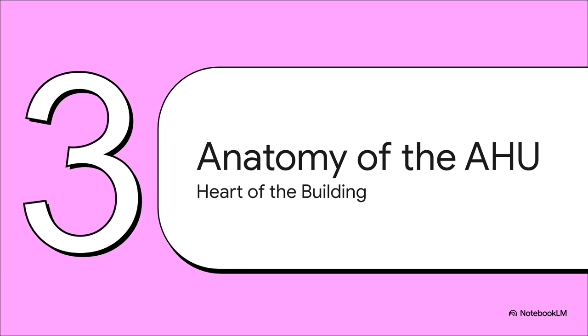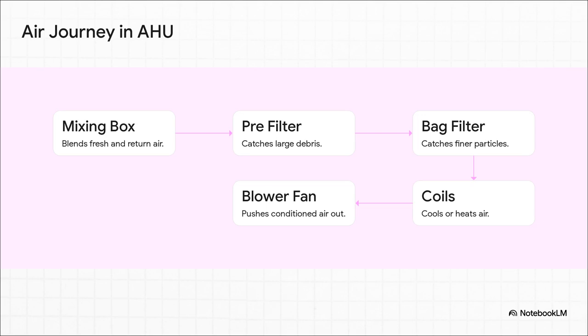Section 3, Anatomy of the AHU, the heart of the building. If we think of the facility as a living organism, the air handling unit, or AHU, is its beating heart. Let's trace a single breath of air through this system. First, it enters the mixing box to blend fresh outside air with return air from the building. Then it hits a coarse pre-filter, typically a G3 or G4 grade, to strip out large debris like pollen or bugs. Next up, a finer bag filter, graded F7 to F9, catches microscopic particles like tobacco smoke before the air sweeps over the cooling and heating coils to reach the exact right temperature. Finally, the blower fan forces this pristine, conditioned air back out into the facility.